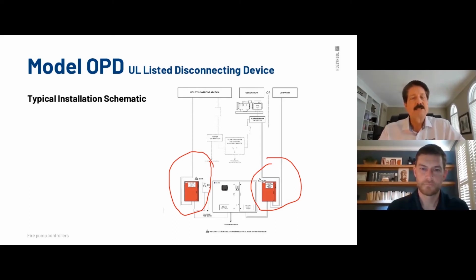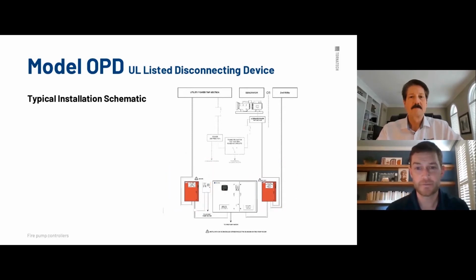And again, it makes common sense to do it properly with the genset too. And Marty, I'll just point out in this typical installation schematic, obviously you can see also that the jockey is tied into the OPD as well. But just say ideally these would be in the pump room as well. I don't know if code says anything about them having to be in the pump room. The same kind of code, where the pump and the control panel have to be within line of sight. I don't think there's anything specifically that says that, but ideally they would be in the pump room as well, just so you can have your eyes on it, knowing that it's off when you're working inside the control panel.